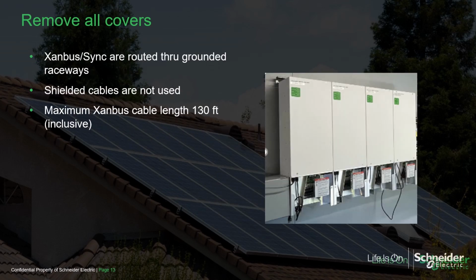When commissioning your system, leave all the covers removed so you can plug in the Xanbus and sync cables and leave them hanging until you verify that all devices are communicating without issue. Some signs of Xanbus instability are missing data fields, or a device may not show up at all.